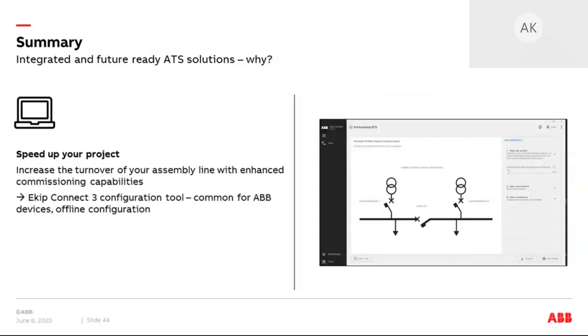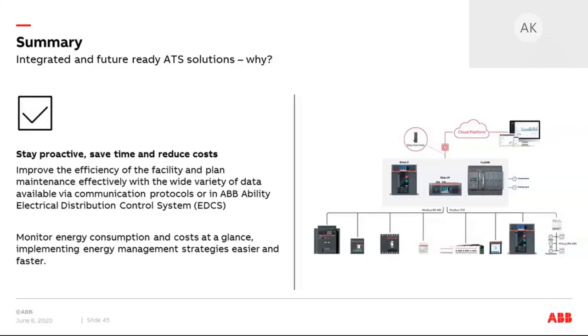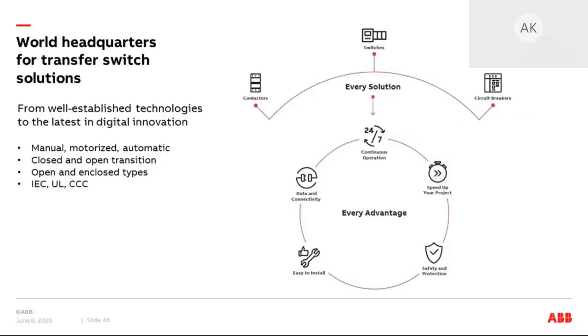With new generation ATS solutions, it will take less time to commission the ATS and put it into operation compared to conventional solutions. Integrated and future-ready ATSs improve the efficiency of the facility and allow you to plan maintenance effectively, thanks to the wide variety of data available via communication protocols or in ABB Ability EDCS — ABB's cloud platform. Data you may receive from the devices includes current, voltage, power, energy, total harmonic distortion, temperature, contact wear, and other diagnostics. ABB offers not only modern ATS solutions but also well-established and proven ones — ABB has a wide portfolio that includes ATSs from 1A up to 6300A based on circuit breakers, switch technology, and contactors.